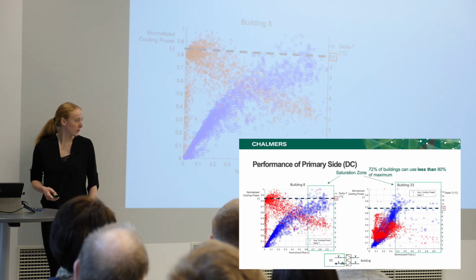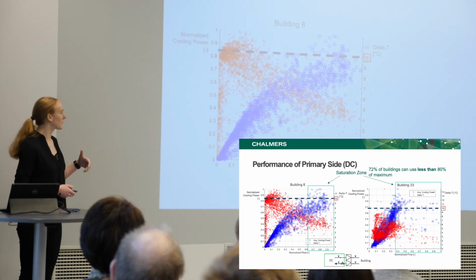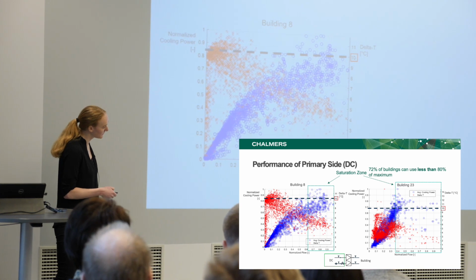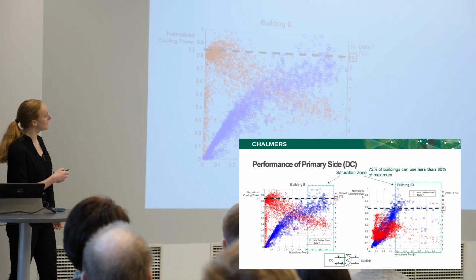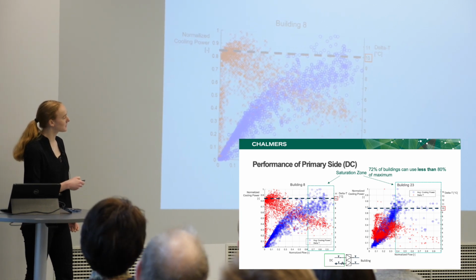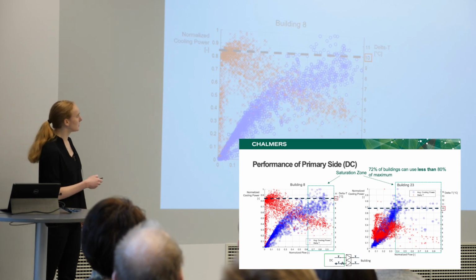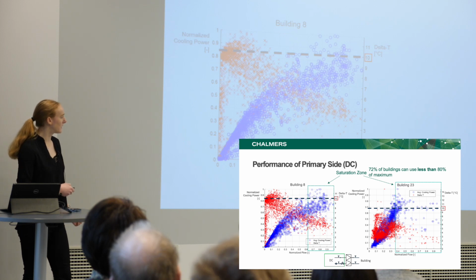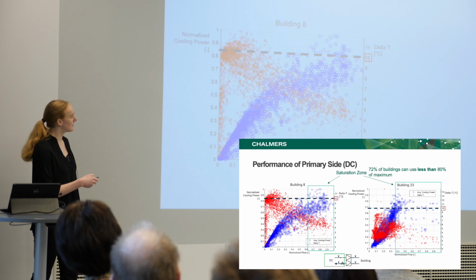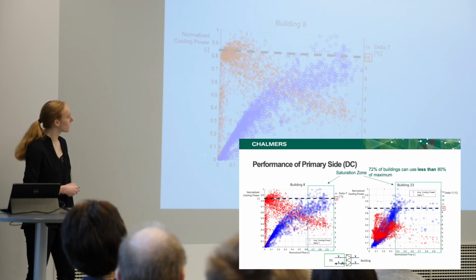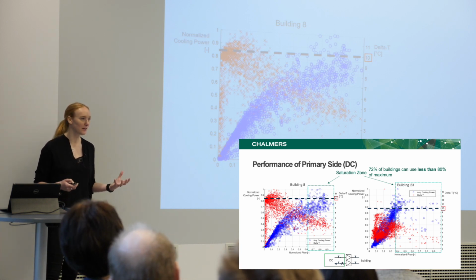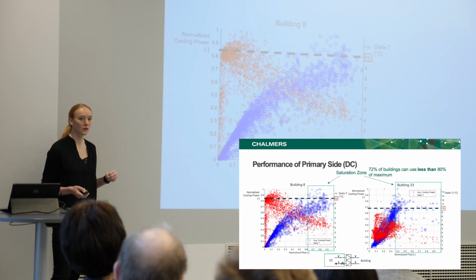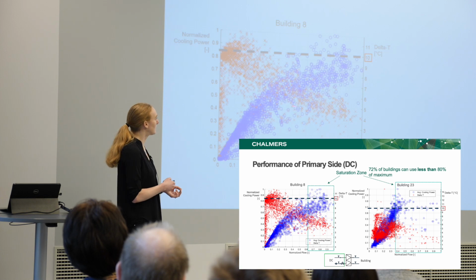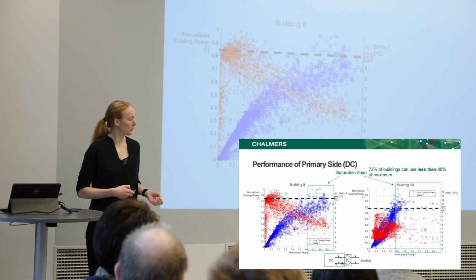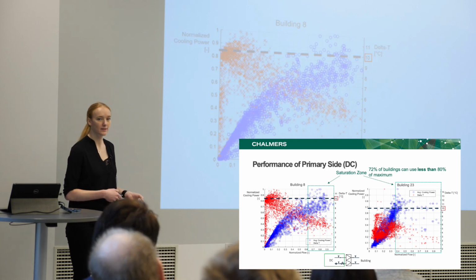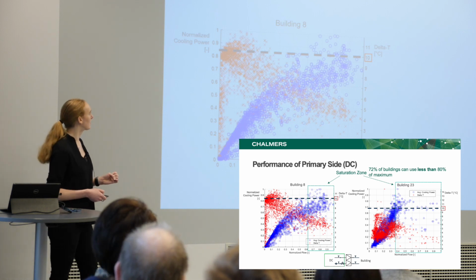And then I also want to show you what it can look like when you compare the performance of different buildings on the primary side only. So here is the temperature data, which is the delta T, these red crosses, and then the cooling power are these blue circles. It's normalized, so divided by the maximum. And you have the flow here, delta T here, and cooling power here. This is a quick way of getting a feeling for how well a substation performs, but also to find out what the trends are for delta T, the temperature difference, which is connected to whether the flow in the building is variable or constant, but it's connected to more things as well.